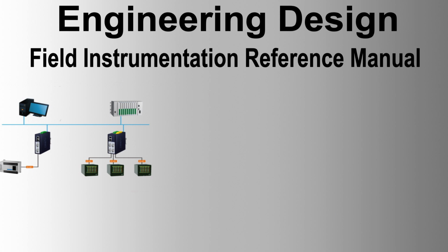IPF trip initiators of SIL 1 and higher should have a red color, and the finish of plant-mounted instruments in oxygen service should be yellow. The finish of all other plant-mounted instruments may be in the manufacturer's standard color, but not red or yellow. Inline instruments must comply with the requirements of the piping class or equipment in or on which the instruments are installed.